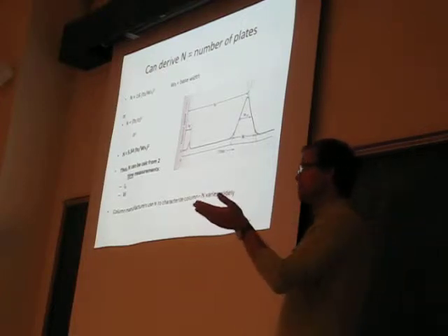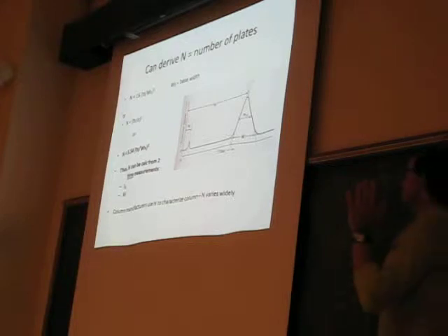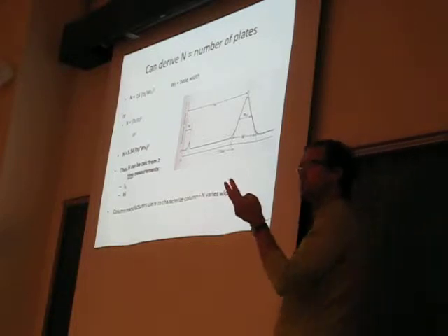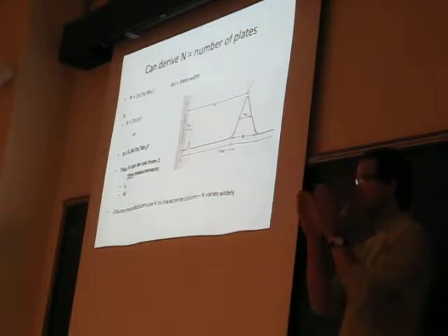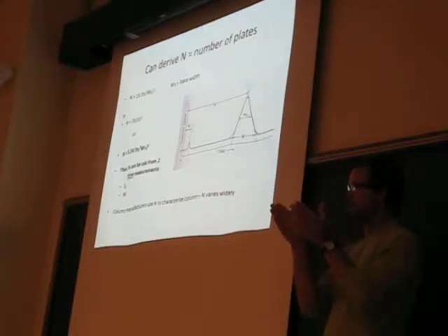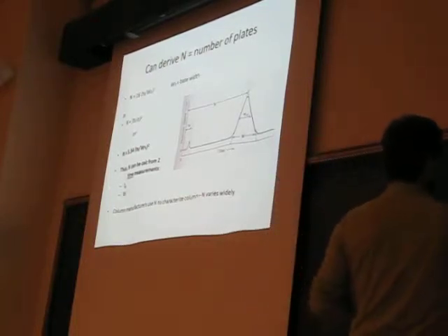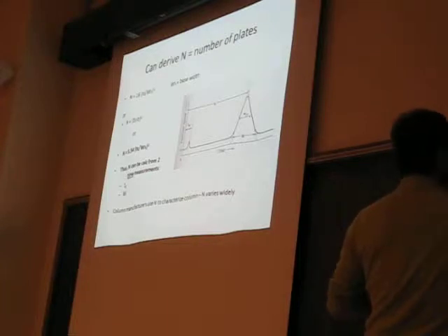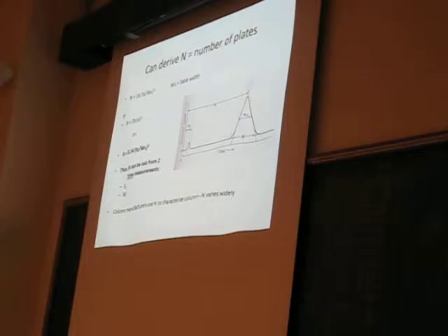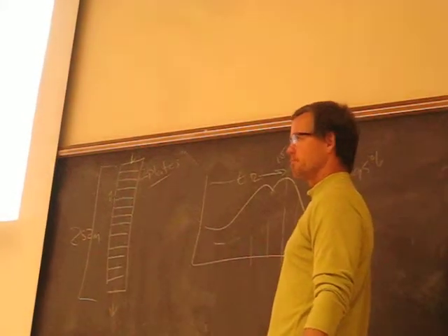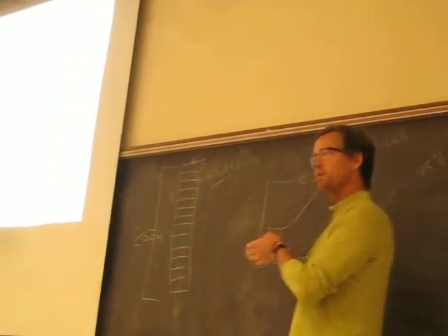And what that might mean is you say, I'm going to run an unknown sample. And when I run my unknown sample, I don't get very good separation of a couple peaks, and I don't know what they are. And I need to separate them adequately so that I can then start trying to determine their identity. And so if the first chromatogram comes out and they're sort of like this, and you know you have two peaks there, then the first thing you can do is say, well, I don't have any money, so I can't buy a new column. So maybe I'm going to change some of the parameters of my mobile phase. That's the only thing I have control over.